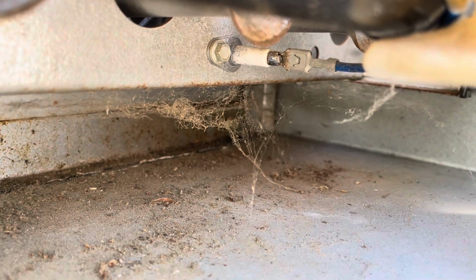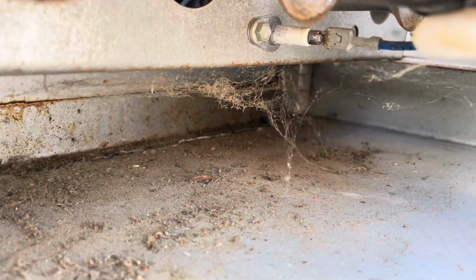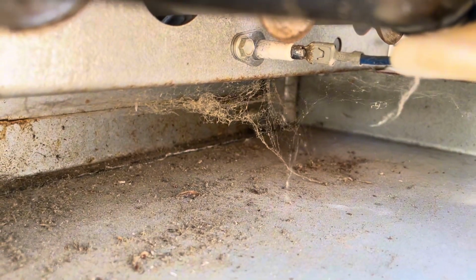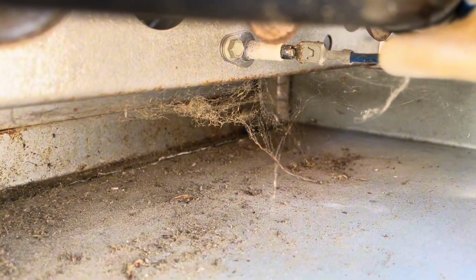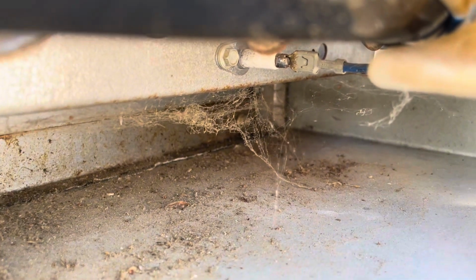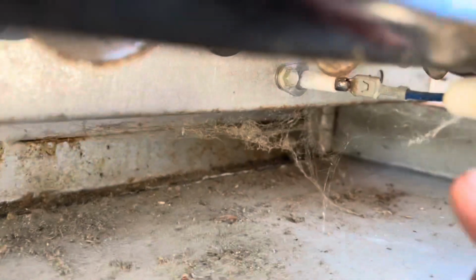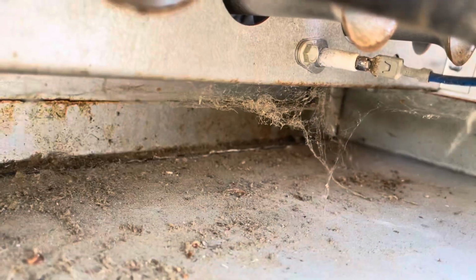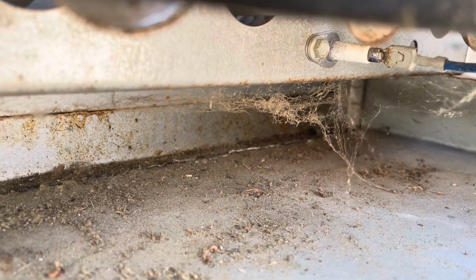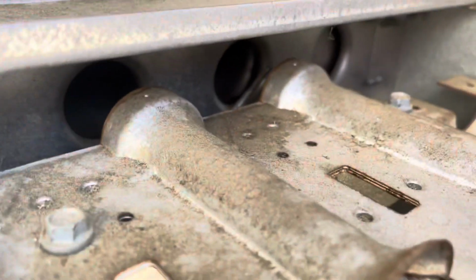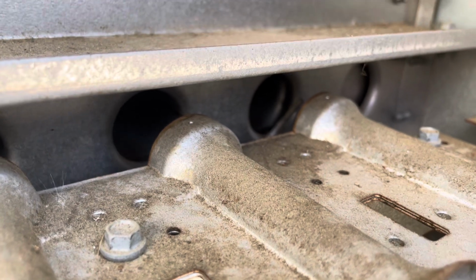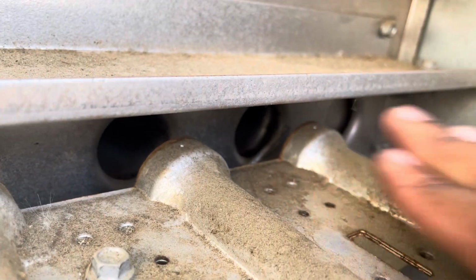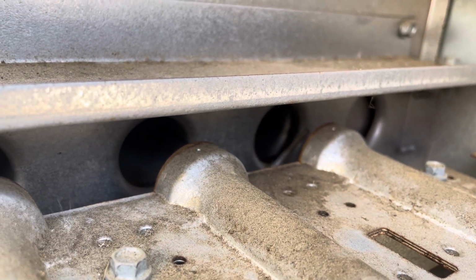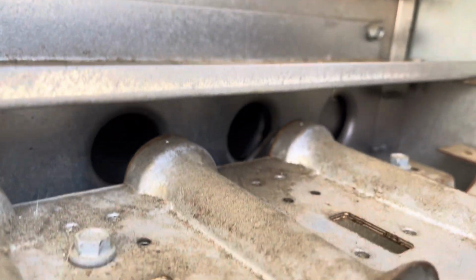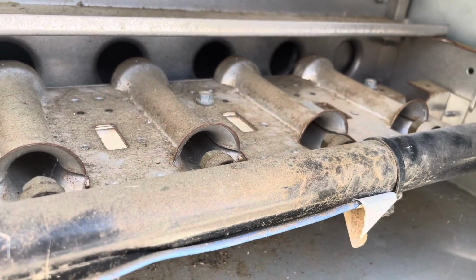That's just a basic breakdown, but that is flame rectification. The flame itself is conducting, or carrying current, which is pretty cool. But check the porcelain. There's the porcelain there. Make sure it's not cracked or anything. Also, the flame sensor rods can get carbon buildup, just because of being exposed to constant flame. You can clean that rod with a Brillo pad or some type of abrasive cloth, or if you have a $1 bill, that works too. But I would avoid using sandpaper, because you can gouge out the actual rod itself.